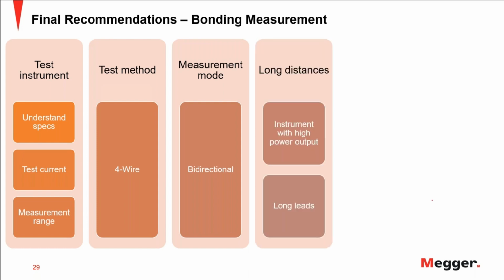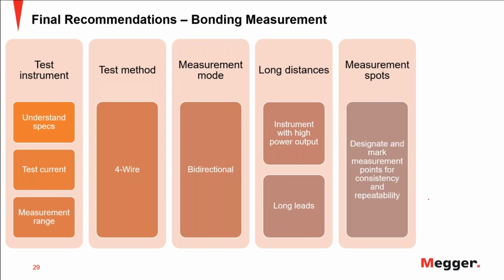So you want to use bidirectional. If you have long distances, you want to use an instrument with a high power output. That means that it's not the same to inject 1 amp with a source of 5 volts, or 1 amp with a source of 10 volts. You have more power there. So you want to use an instrument that has higher power, meaning not only the current, but also the voltage. And you need to have some long leads if you have this situation of long measurements, long distances.